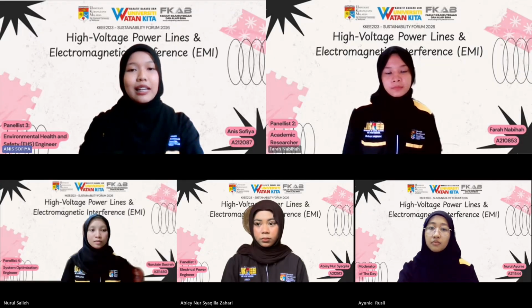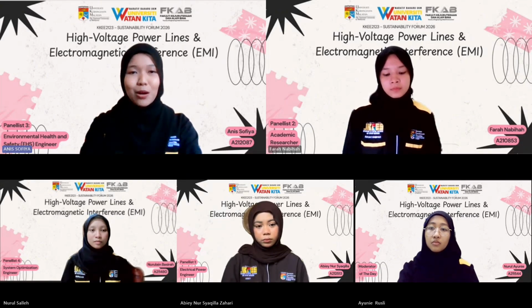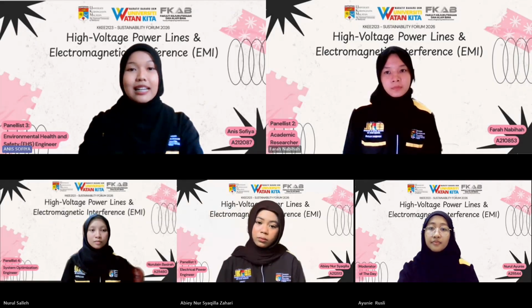EMI can affect protection and automation systems that keep the power grid operating safely. One example is false tripping, where a protection relay incorrectly detects a fault and disconnects a power line even though there is no actual problem. EMI can also cause a failure to trip, where the relay fails to detect a real fault. This may lead to equipment damage and safety risks.